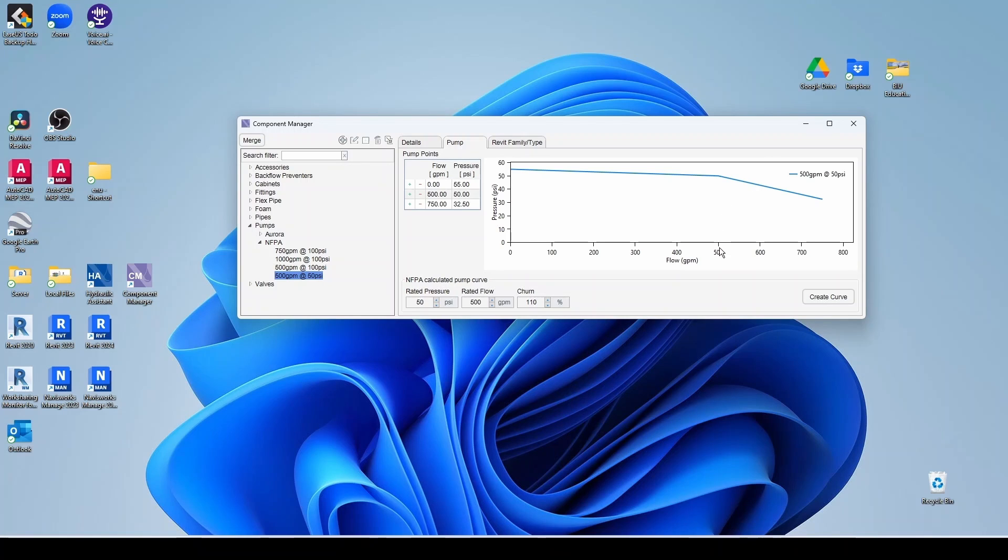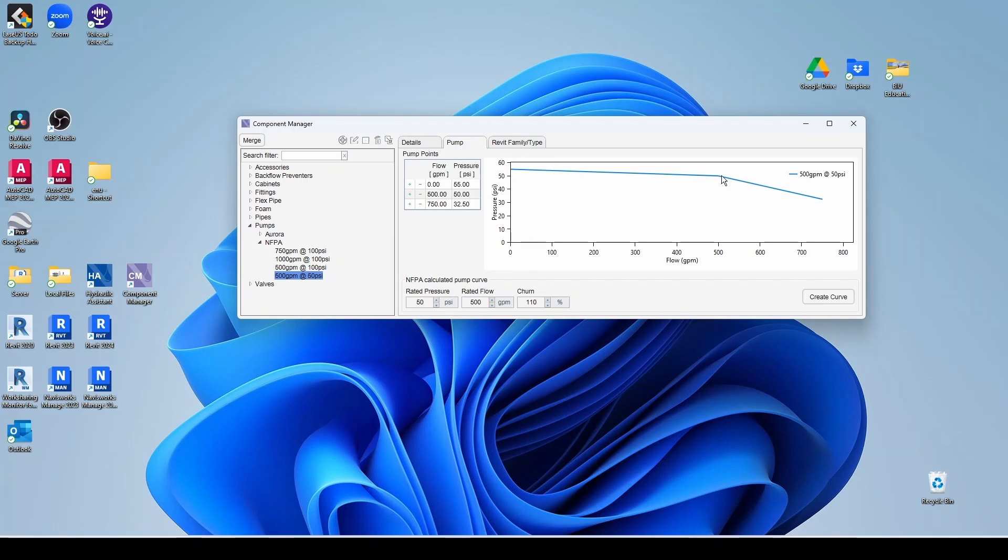So at 500, I have 50 PSI. Then at zero, I have 110% for my churn, which is 55 PSI. And then it added another point at 150% of my flow, which is I believe 65% of the rated pressure. So that's our NFPA pump. Perfect.